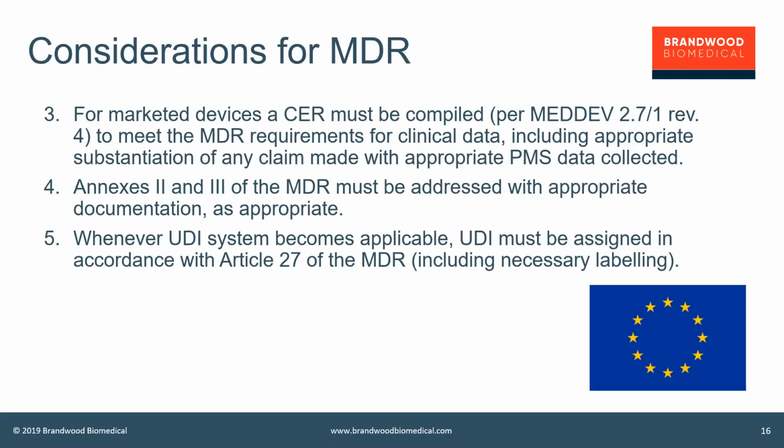That's one way. Two, any post-market surveillance data that you're getting. Now, this is a big one because not only do we know that the MDR is changing and being more scrutinizing around the PMS information, but we know that there are guidances coming from TGA. We know there's more scrutiny at the FDA in the post-market surveillance piece. So this is something that updating your CER to ensure that all of your post-market surveillance data, not only the stuff that you report to the regulators, but also the complaints that you hold internally, is captured within that CER.